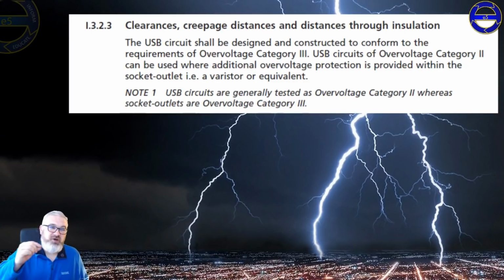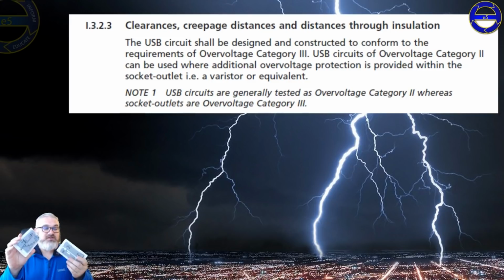However, there's a section in Part I which I found really interesting. I can't get an answer from a manufacturer. The USB circuit shall be designed and constructed to the requirements of overvoltage category 3. Well, that's cracking, that's great, that's local protection. USB circuits of overvoltage category 2 can be used where additional overvoltage protection is provided within the socket outlet, i.e. varistor or equivalent. Now I can tell you now, of all of the socket outlets I have, none of them tell me what the overvoltage protection category is, or give any indication of varistors or any other equivalent overvoltage protection.